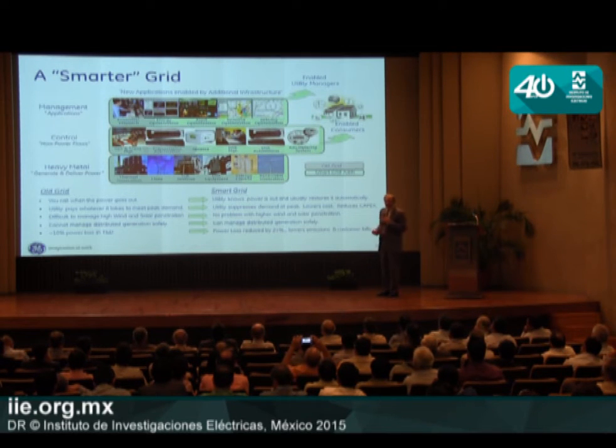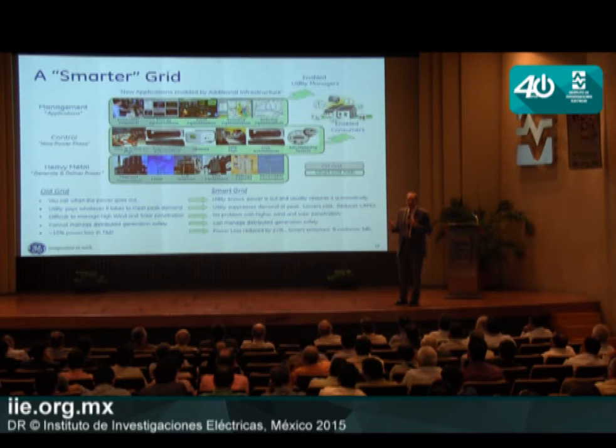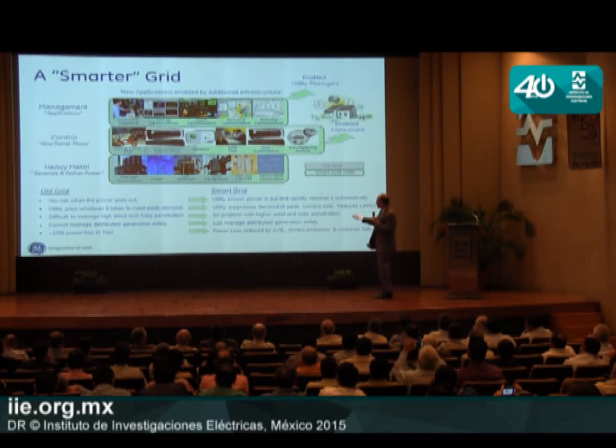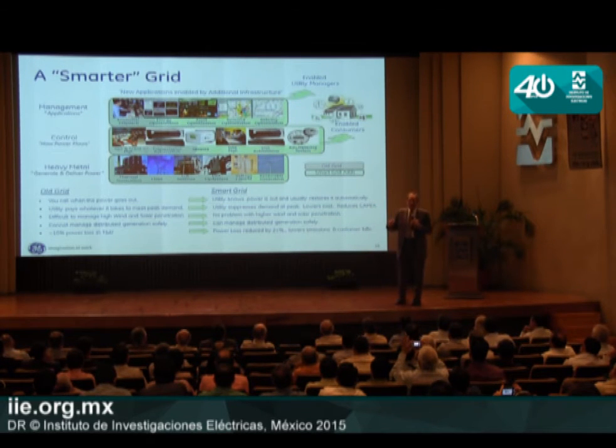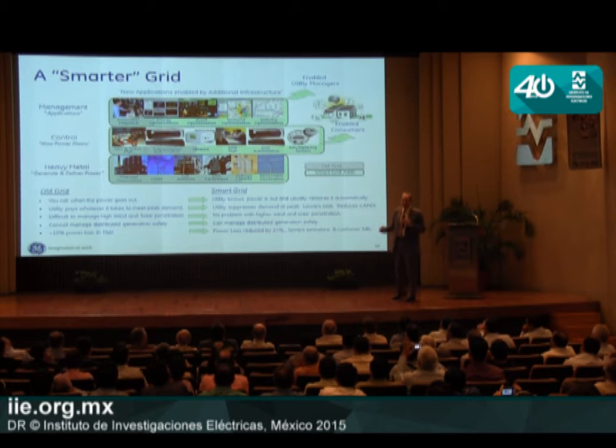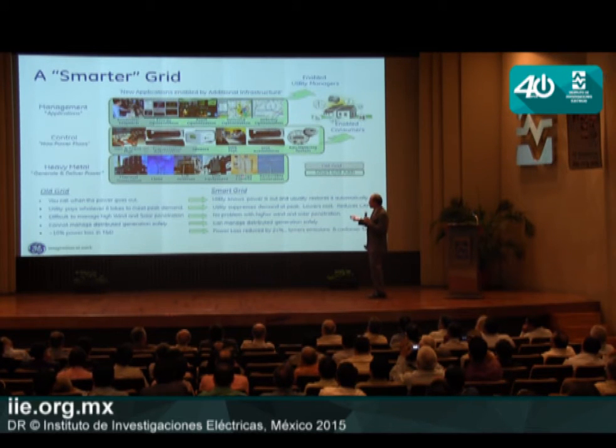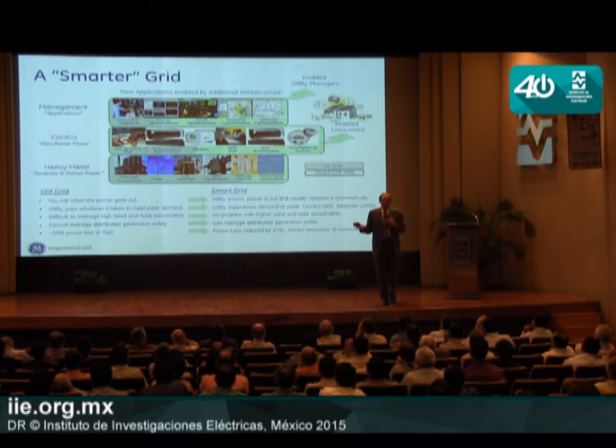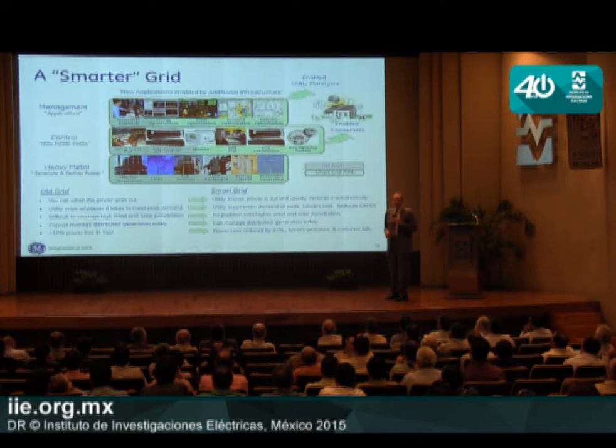We're doing voltage control now, which has a stronger business case. Instead of doing voltage control by itself, we're integrating it with VAR control, reactive power control, into integrated volt-VAR control. Voltage is directly proportional to load, so when I control voltage, I manage load. We've been using voltage control to manage load so the utility doesn't exceed a previous peak load condition. But we also know reactive power, VARs, is directly proportional to losses. We reduce losses on the grid through reactive power control. When we integrate these two together, the benefits are much greater in integrated volt-VAR control.